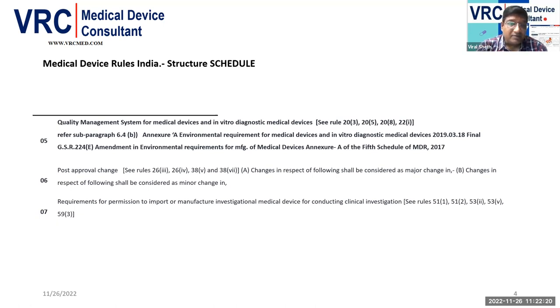Schedule 7 is applicable for the requirements for permission to import or manufacture investigational medical devices for clinical use. This means when you are importing any device that doesn't have a predicate device in India, or if we want to manufacture the device in India and don't have any such device - in those cases, if it falls under the clinical investigation requirement, we should follow Schedule 7 requirements.